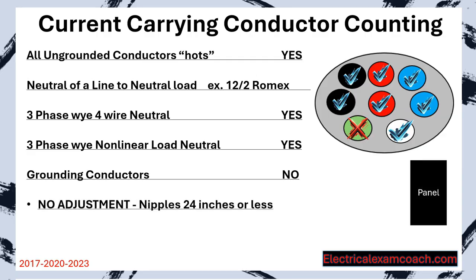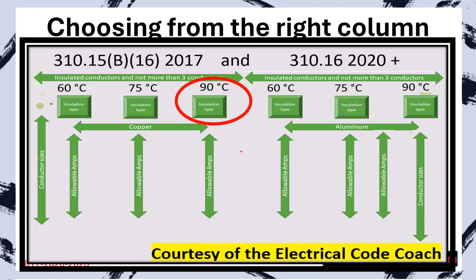No adjustment will be made if we have nipples that are 24 inches or less. Imagine we have a panel on the right and a panel on the left — we run a short nipple that's 24 inches or less; this does not count in our bundling adjustment. Now, when it comes to choosing from the right column: up until this point we've chosen most of the time from the 75 degrees C column, but 99% of the time when doing bundling adjustments or temperature corrections, we're going to choose from the 90 degrees C column.